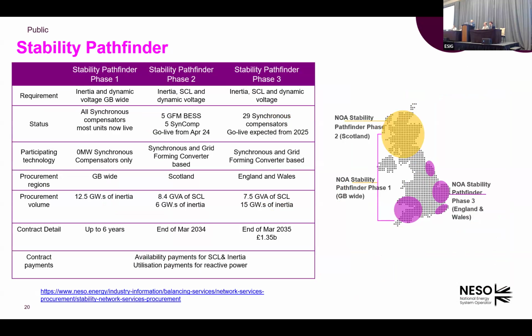Since we developed the technical requirement for grid forming, for people to get into the market there should be a market mechanism for them to participate. That's the reason we went through a Pathfinder process. How it works is we've done a lot of system study, identifying the different system needs in terms of inertia requirement and system strength requirement.